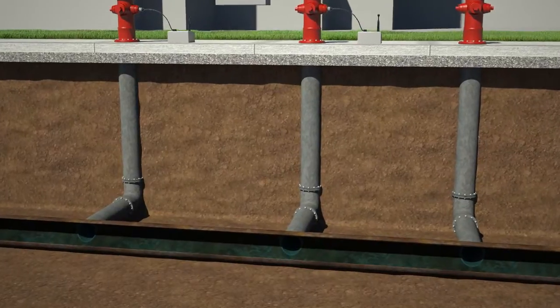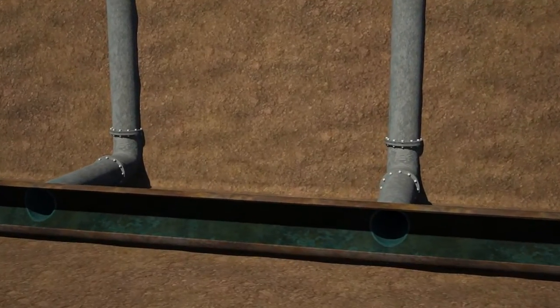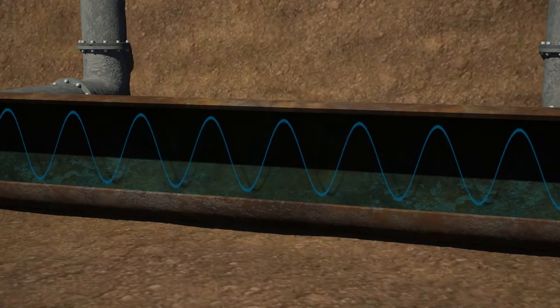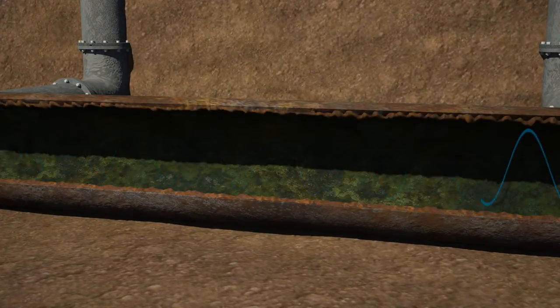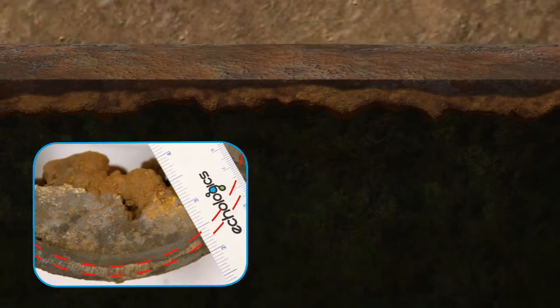The speed at which the sound wave travels is dictated by the condition of the pipe wall. The better the condition of the pipe wall, the quicker the sound travels. As the pipe wall deteriorates, degradation and corrosion cause sound to travel measurably slower.